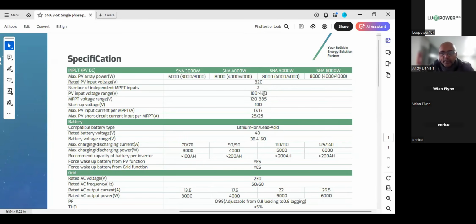So this is open circuit voltage. In other words, with no load connected, it should be that. But with load connected, you cannot exceed 385 volts. The chances of you getting to 385 with 8 panels connected under load is highly unlikely. But we've seen cases where guys do that because they exceed the number of panels here. They're not focusing on the fact that you can't in any instance exceed any one of these, right?